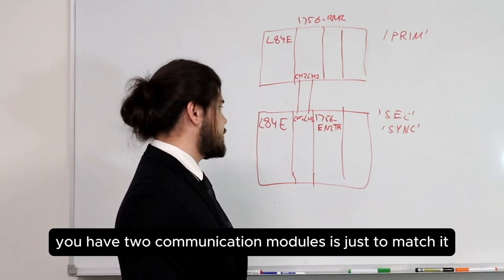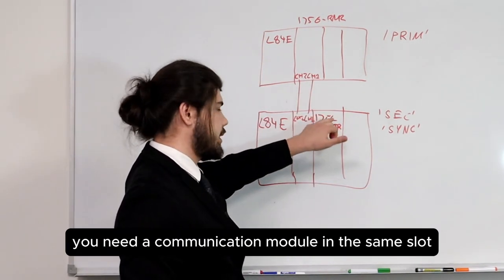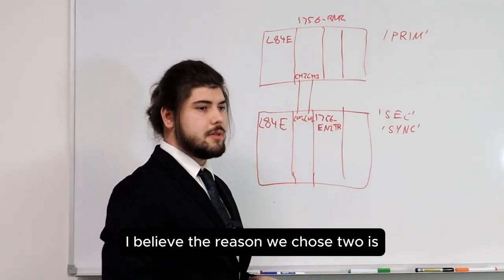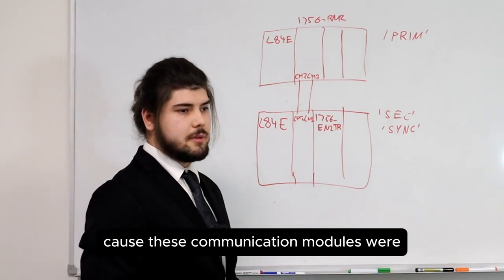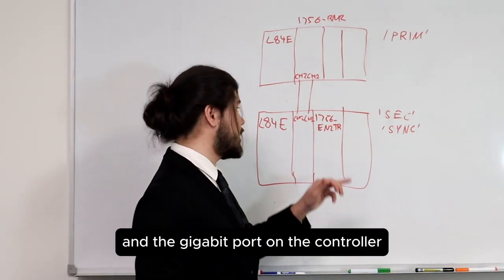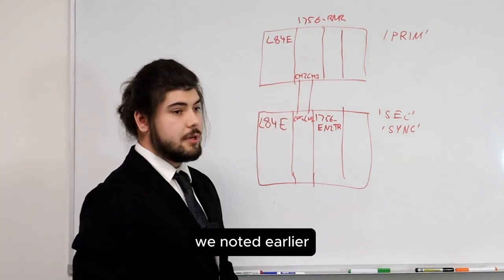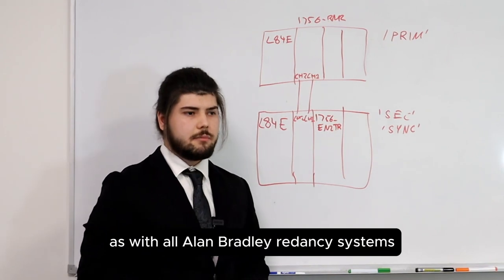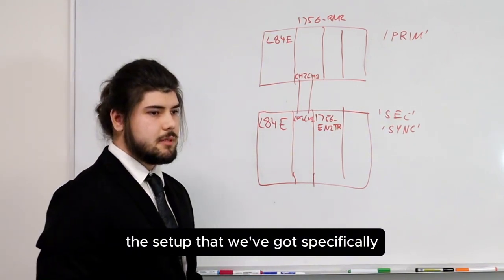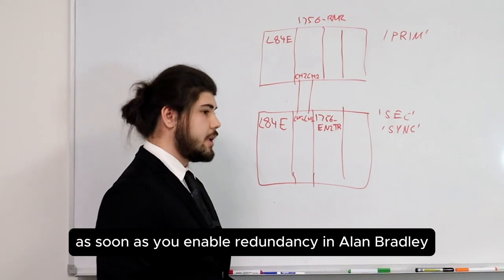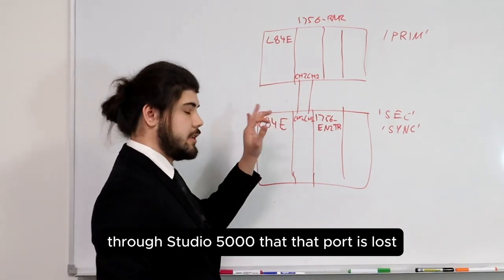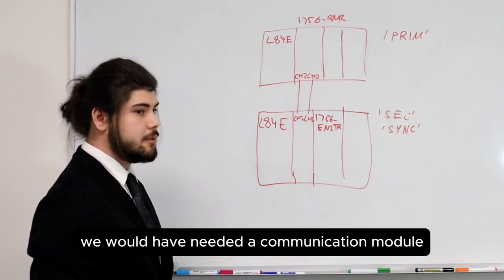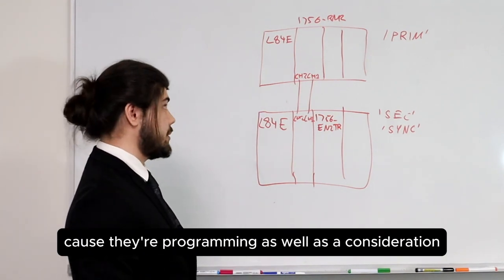The reason we have two communication modules is to match slots for both chassis. You don't necessarily need two, but we chose two due to port speed — these communication modules were 100 megabit per second. The gigabit port on the controller was not able to be used in a redundancy system; that's a constraint with all Allen Bradley redundancy systems. As soon as you enable redundancy in Allen Bradley through Studio 5000, that port is lost — you can no longer communicate with it. So regardless, we would have needed a communication module even if we didn't have remote IO.